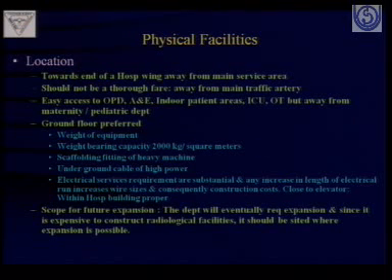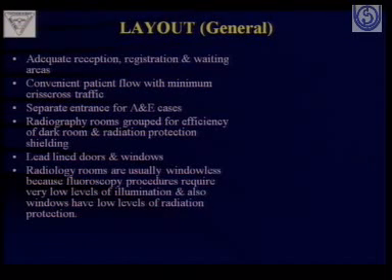The location: as you are aware, there is heavy equipment involved in this, plus the radiation safety requirements, so it's better to be on the ground floor where you can have separate generators, consoles, and also a substation for this purpose. Weight of equipment is a very important aspect. So various cabling requirements are there, and the need for CT and MRI is there, so future expansion needs are also taken care of. Adequate reception should be there, with convenient patient flow and minimum crisscross traffic.